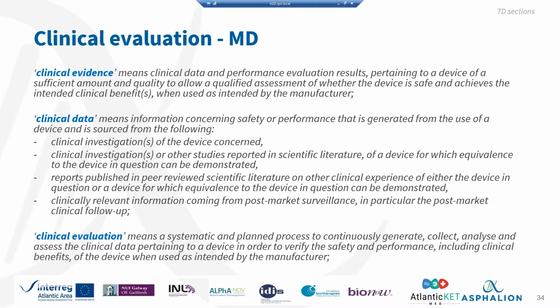Reports published in peer-reviewed scientific literature or other clinical experience of either the device in question or a device for which equivalence to the device is demonstrated, or clinically relevant information coming from post-market surveillance. Okay, clinical data can come from several places. It doesn't only make reference to data generated in clinical investigations. It can also come from literature, and it can come from post-market surveillance activities. Okay. This has to be kept in mind.